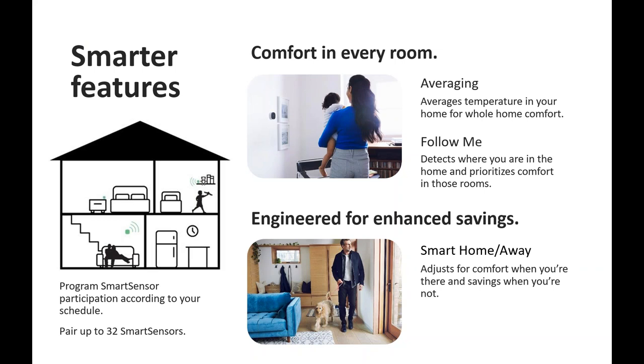Andrew asks if sensors will help with a tri-level home. To an extent — if you've got an extreme temperature difference like 10 degrees between the basement and upstairs on one zone, it's only going to help within a few degrees. If it's within about four or five degrees, it's really going to help balance the comfort out. If it's beyond five degrees, closer to 10 degrees difference, this isn't going to do the trick — you've got bigger issues and you're always going to be better off zoning it or figuring out why there's such a big difference.